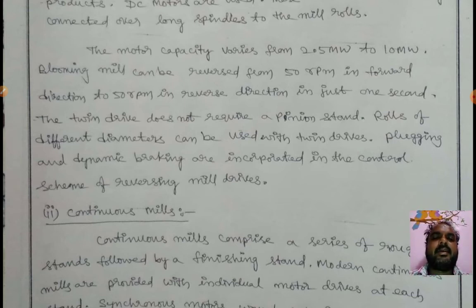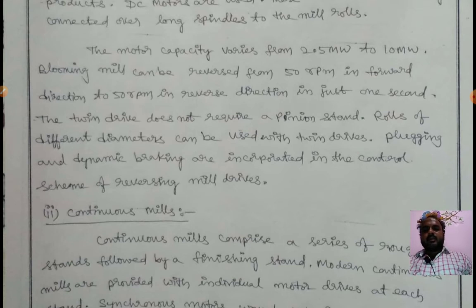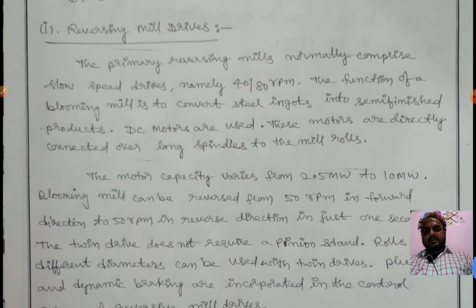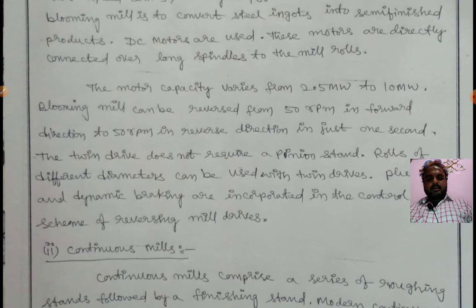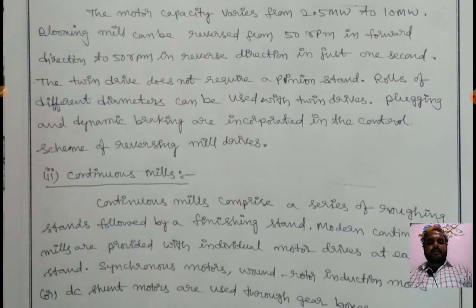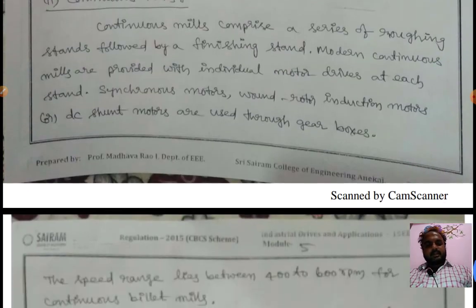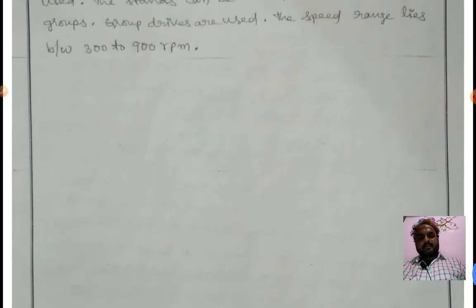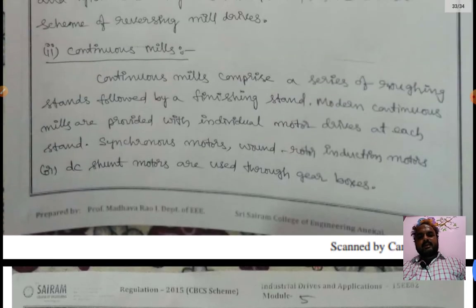The motor capacity varies from 2.5 megawatts to 10 megawatts. Blooming mills can be reversed from 50 RPM in forward direction to 50 RPM in reverse direction in just one second. Plugging and dynamic braking are used in this type of mill.